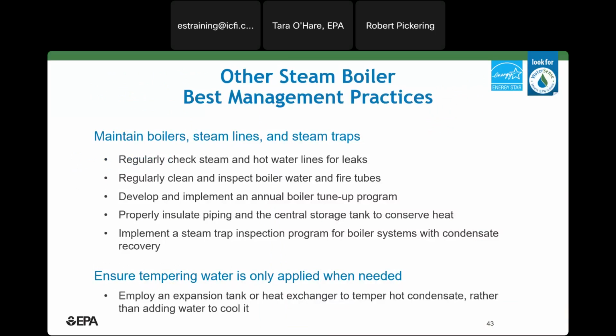Aside from installation of a condensate recovery system, the key to an efficient boiler operation is to keep all the components in good working order. You'll want to check steam and condensate, steam and water lines for leaks, and check to make sure that steam traps are functioning properly. You'll want to regularly clean and inspect the boiler water and fire tubes for good heat transfer and tune up the boiler for efficient firing. Make sure steam lines and condensate return lines are properly insulated to prevent heat losses.